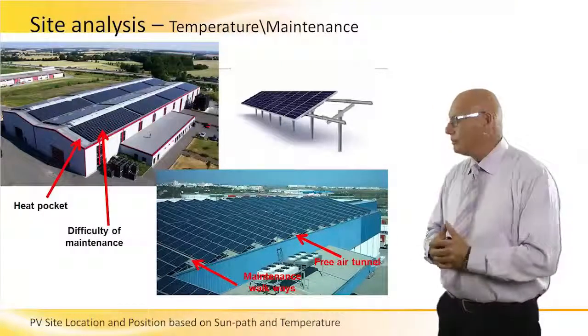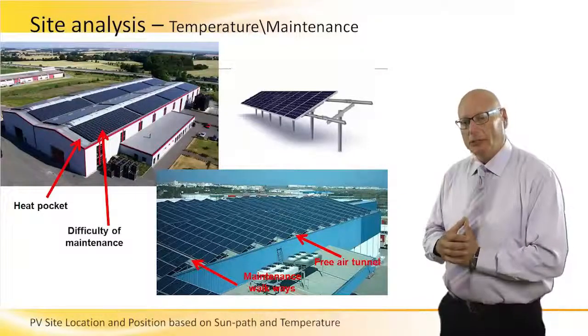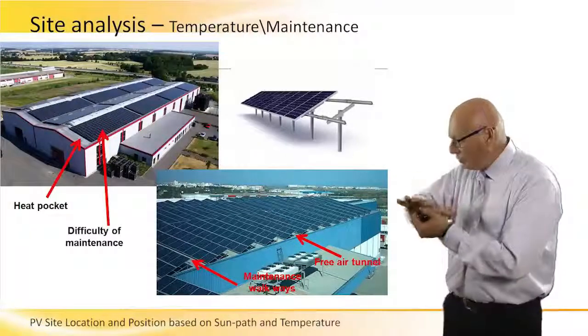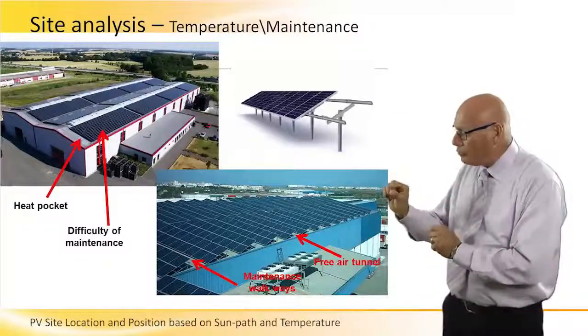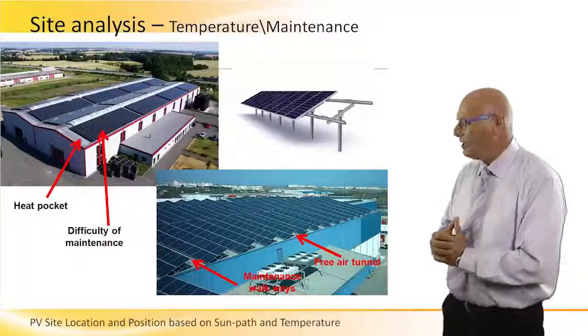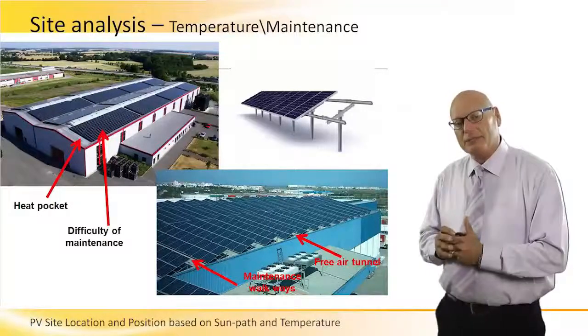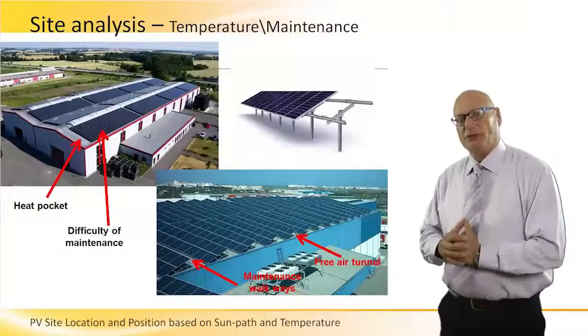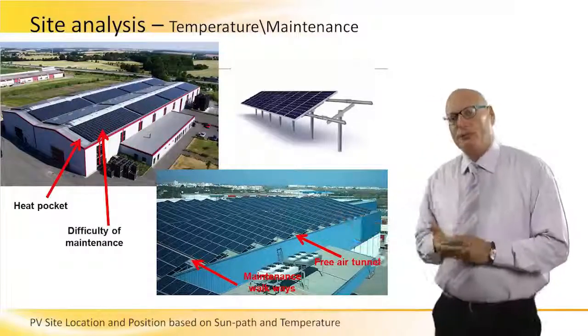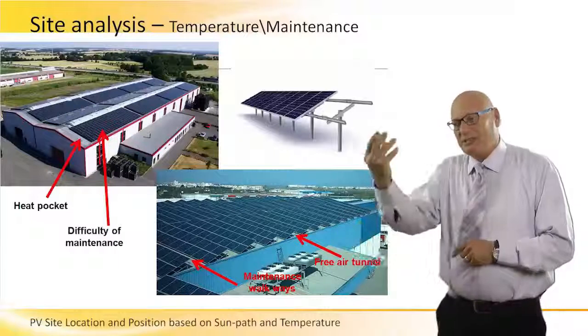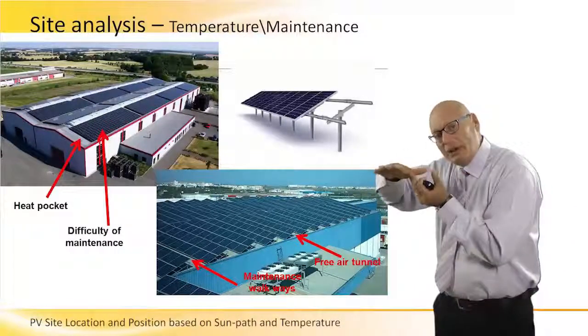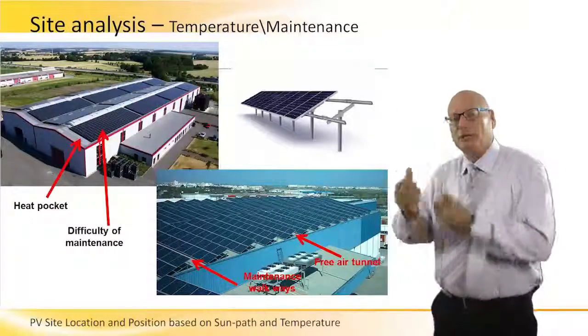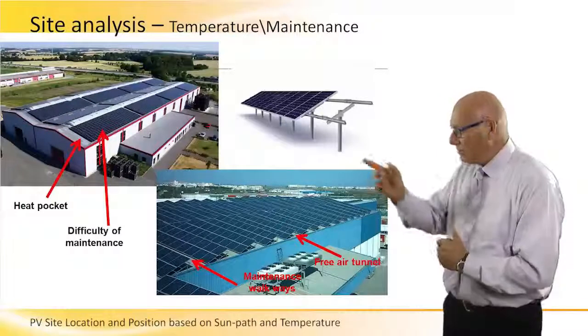Look at the heat pockets on the top left — a factory with large arrays. No spaces between one module and another — it's just like a huge plate, very close to the roof itself, creating heat pockets. Not only is it creating heat pockets, but the area of the roof not covered by panels gets hot, and that hot air is dissipated from underneath the panels. Since we have a continuous homogeneous layer of panels, the heat waves have nowhere to go — they just go up and hit the backside of the panels, lowering efficiency. This is a very bad example.